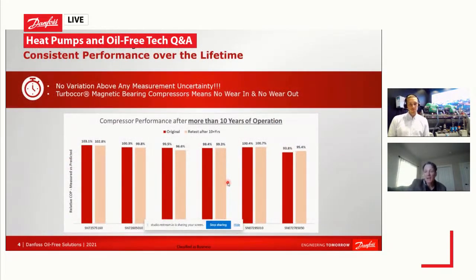The other benefit of the technology that he didn't recognize, and the team of engineers that created this technology at the time didn't really recognize, was that HVAC systems degrade in performance over time. And the two main factors that drive that performance degradation are those same factors that result in the lack of reliability with oil in the system, and also the metal-to-metal contact that I mentioned was a primary noise generator. If you have neither one of those, which the Turbocor compressor and the oil-free system do not, then you shouldn't have any performance degradation over time or significant performance degradation over time. But that only matters if we can prove it. And so that's what we've been working to do over the last few years.